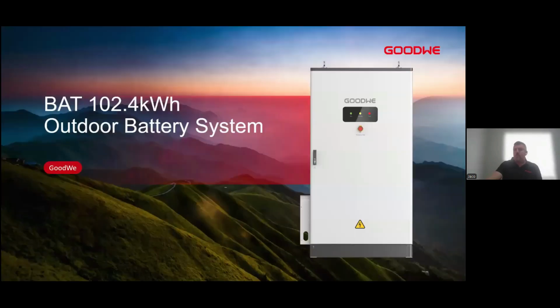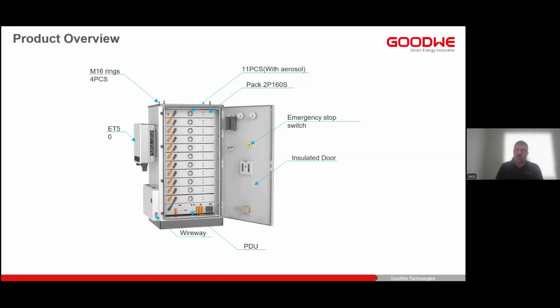Right. So then taking a look at the GoodWe battery offering. First up is our 102 kilowatt hour outdoor solution. This is a fully self-contained all-in-one battery solution. As you can see, there is a built-in fire suppression system with aerosol. And the inverter typically mounts on the side of the battery cabinet. It is fully outdoor rated with an IP55 rated enclosure. And then you have an insulated door and a heat resistant door, as well as an air conditioning unit at the back that will achieve forced air cooling for the battery bank.